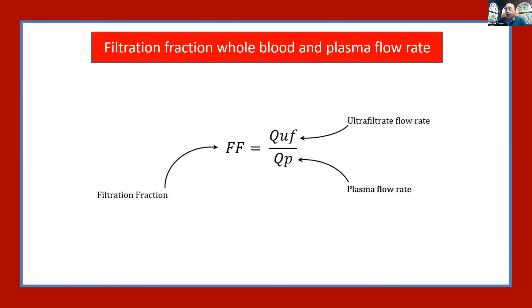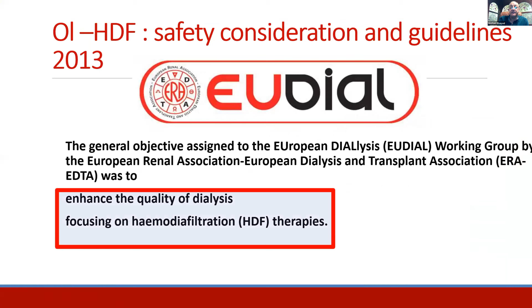The filtration fraction is another piece of information we should know, meaning the percent of the ultrafiltration relative to either the blood or the plasma flow. Take into consideration the blood flow. For example, if you are using an ultrafiltration rate of 100 and a blood flow of about 300 mL per minute, the filtration fraction is 33%. In all scenarios, a filtration fraction above 30% is a risk for the dialysis circuit. So usually the filtration fraction should be above 20% and less than 30%.